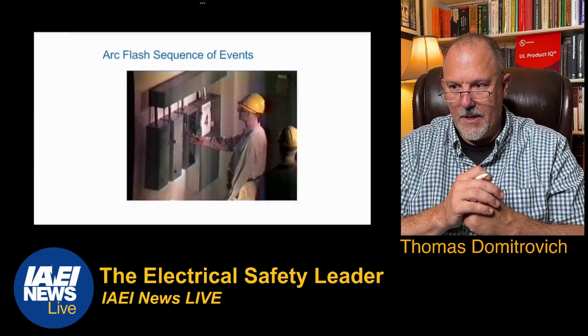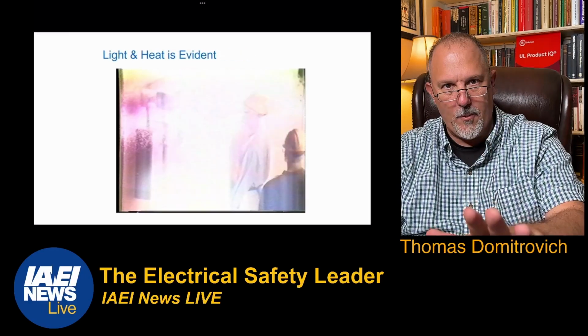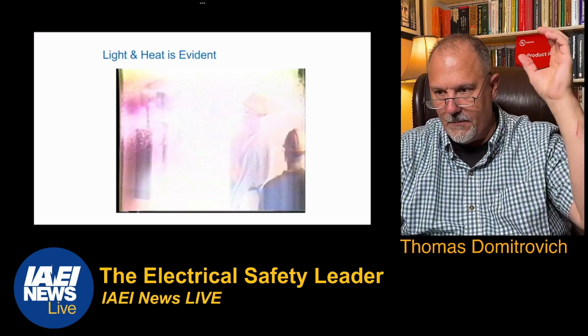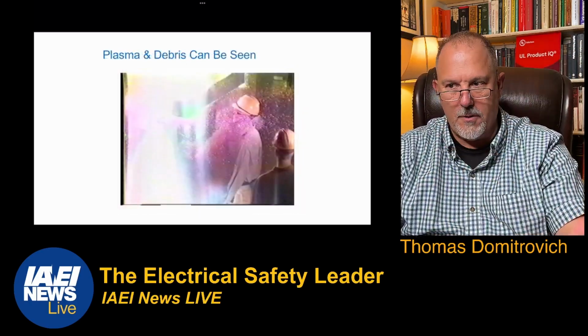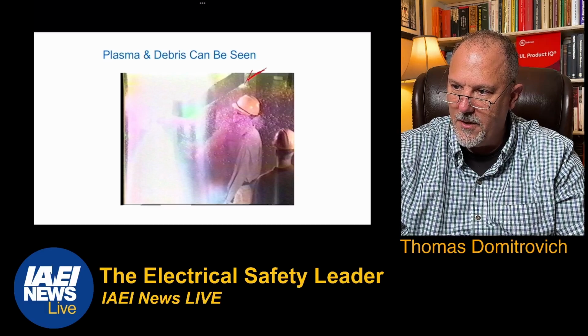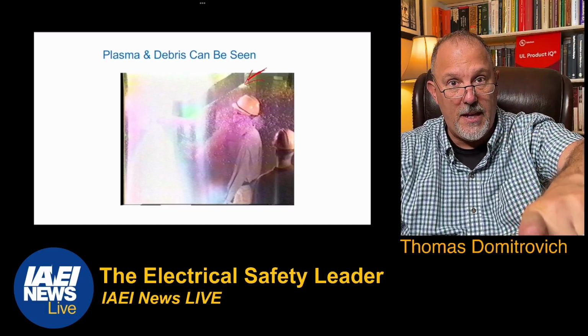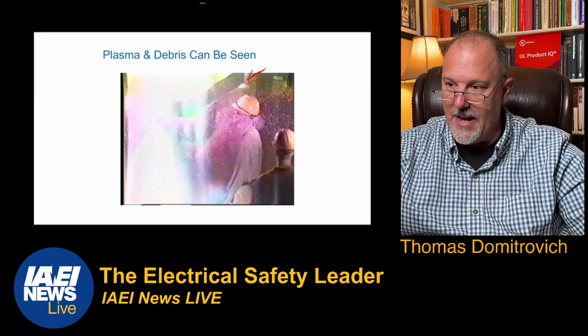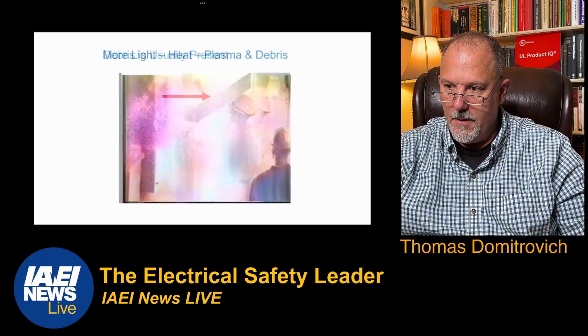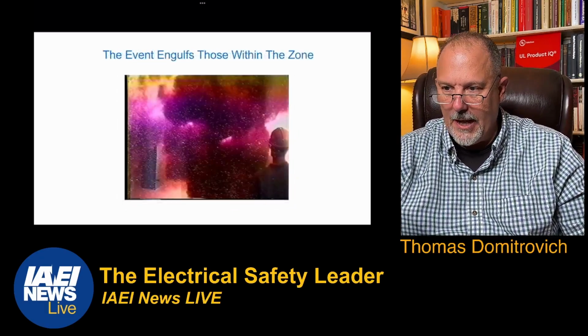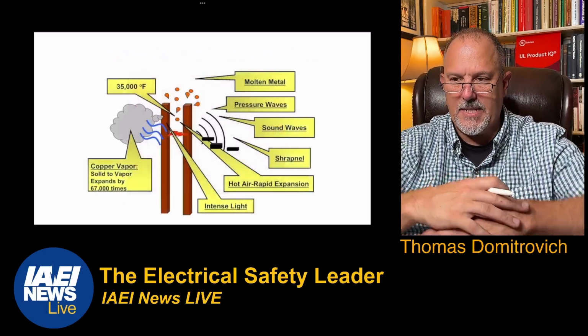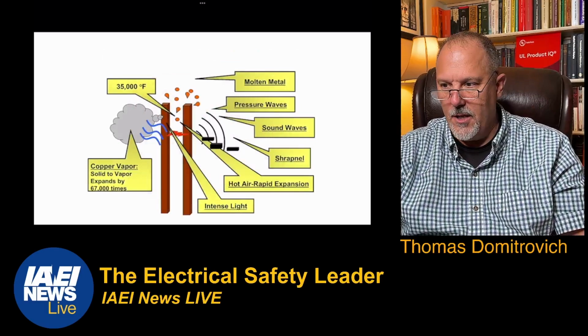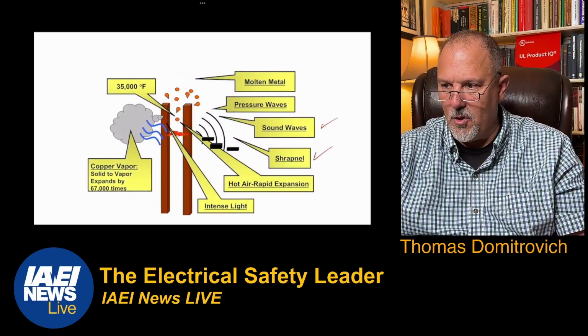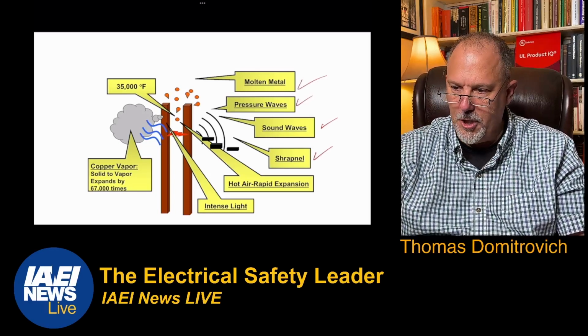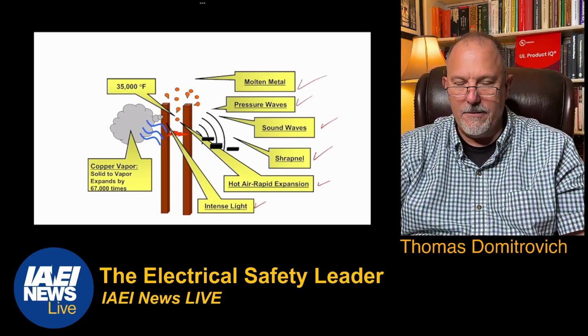So that video showed basically a sequence of events. You had the initiation. Remember, we talked about this. You initiate the fault. It causes the plasma. The current flows through the plasma. What we didn't anticipate was the trough being blown off, not because of the pressures, but because of the cable whip in that trough. All of the light, all of that heat, all of the gases basically fill that room, and you have a lot of pressure, a lot of sound. You have sound, shrapnel, pressure, molten metal being spewed, intense light, and hot air, heat.